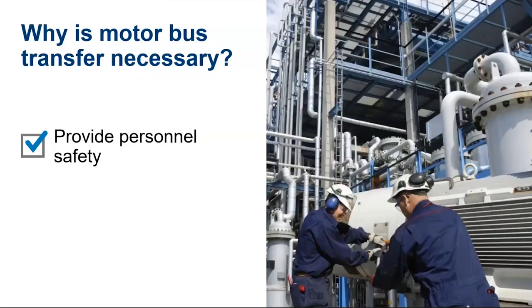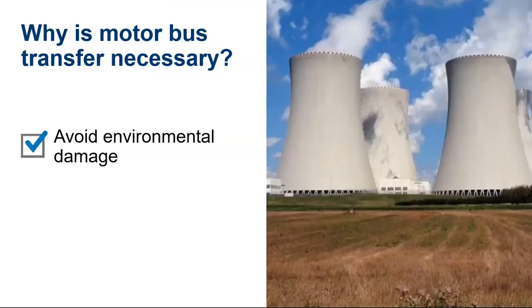Hazardous conditions can quickly arise when there is loss of power during an industrial process, putting personnel lives at risk. The most important one is also the environmental damage that could be caused due to loss of process. This can have severe consequences that can last for decades. For example, in a nuclear power plant, loss of power can result in loss of critical functions like the cooling system. The cooling system's primary function is to pump water into the reactor to regulate its temperature. If this process stops, the reactors can quickly overheat, causing meltdowns, environmental damage, and personnel lives at risk.